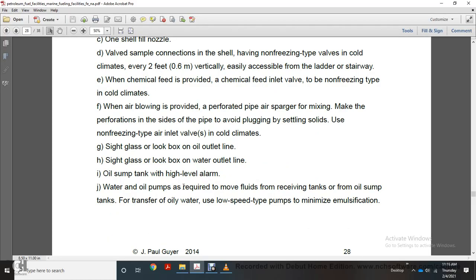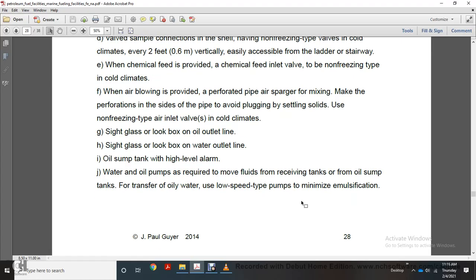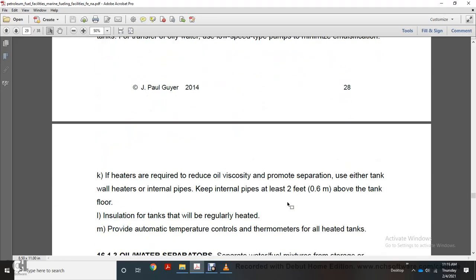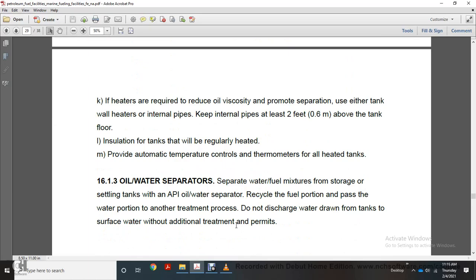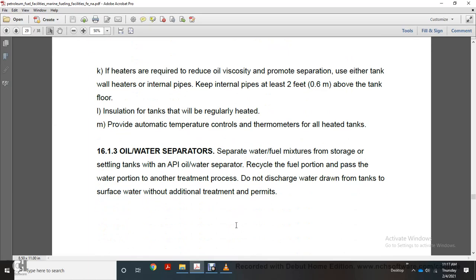Water and oil pumps. Water and oil pumps are required to move the fluids from the receiving tank to the oil sump tank. Transfer oil and water using low speed type tank pumps to minimize emulsification. If heaters are required to reduce oil viscosity and promote separation, use tank wall heaters with internal pipes kept at least 2 feet above the tank floor. For tanks that will be regularly heated, provide automatic temperature control with thermometers for all heated tanks.